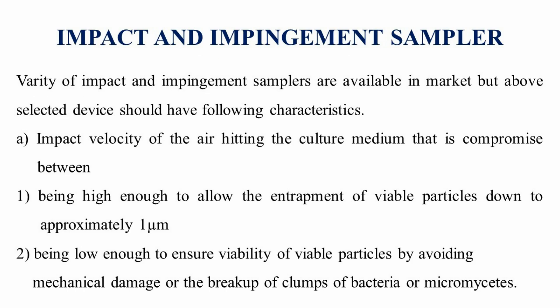A variety of impaction and impingement samplers are available in the market, but the selected device should have the following characteristics. First, the impact velocity of air hitting the culture medium should be compromised between: being high enough to allow the entrapment of viable particles down to approximately 1 micrometer, and being low enough to ensure viability of viable particles by avoiding mechanical damage or the breakup of clumps of bacteria or micromycetes.